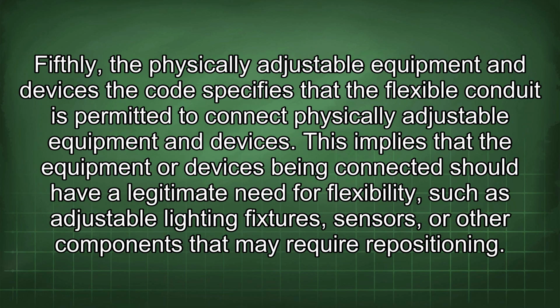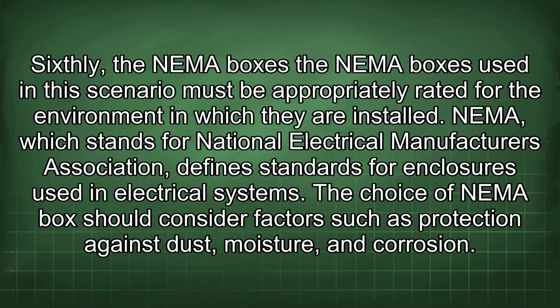Fifthly, the physically adjustable equipment and devices. The code specifies that the flexible conduit is permitted to connect physically adjustable equipment and devices. This implies that the equipment or devices being connected should have a legitimate need for flexibility, such as adjustable lighting fixtures, sensors, or other components that may require repositioning. Sixthly, the NEMA boxes. The NEMA boxes used in this scenario must be appropriately rated for the environment in which they are installed. NEMA, which stands for National Electrical Manufacturers Association, defines standards for enclosures used in electrical systems. The choice of NEMA box should consider factors such as protection against dust, moisture, and corrosion.